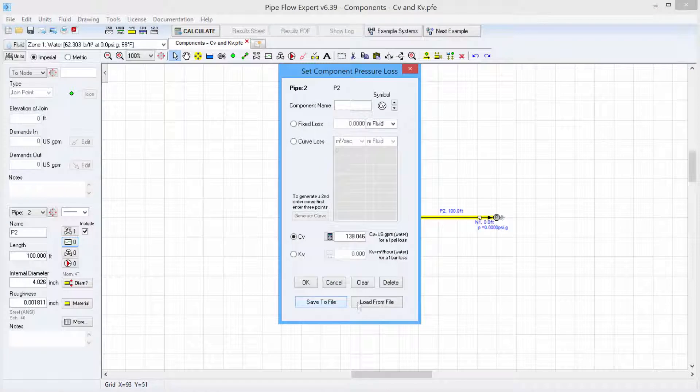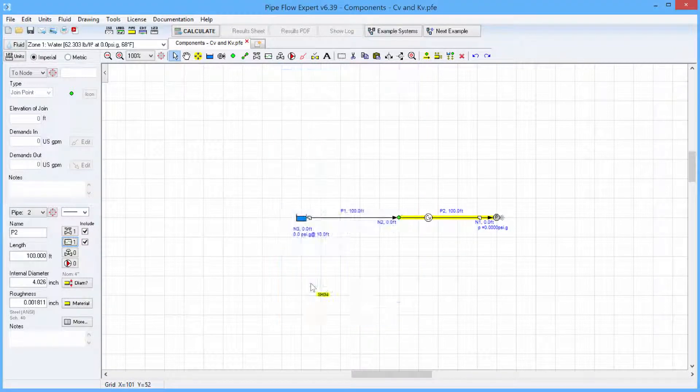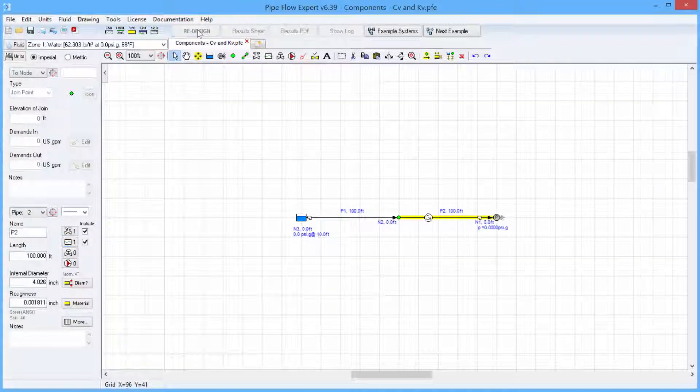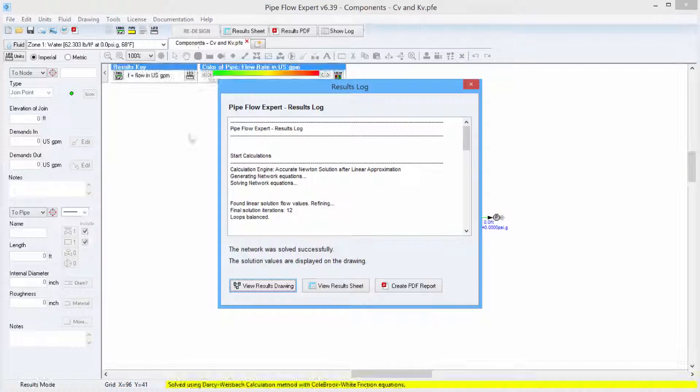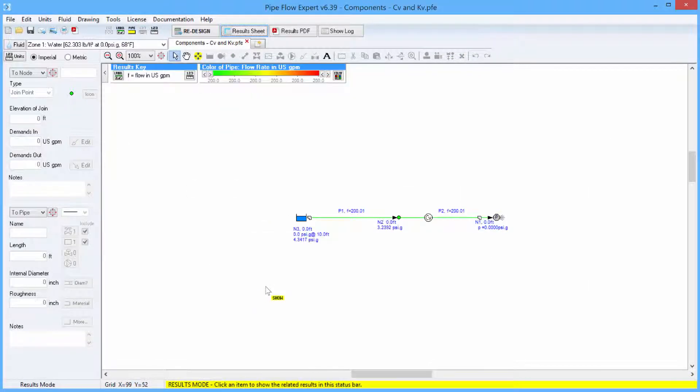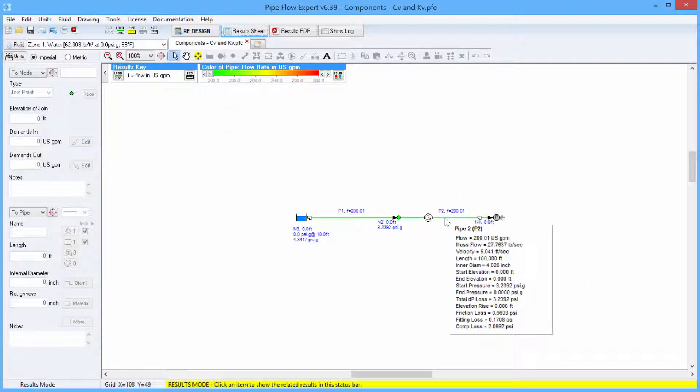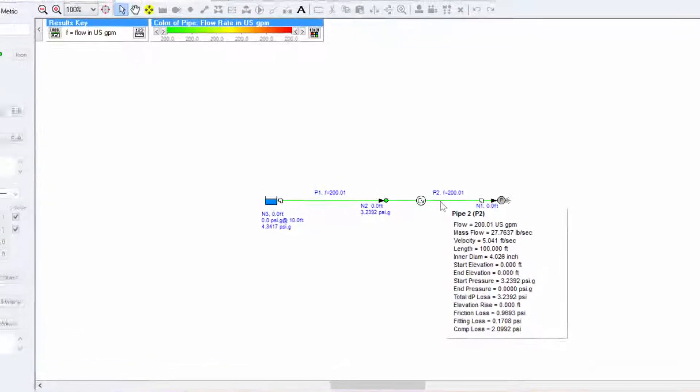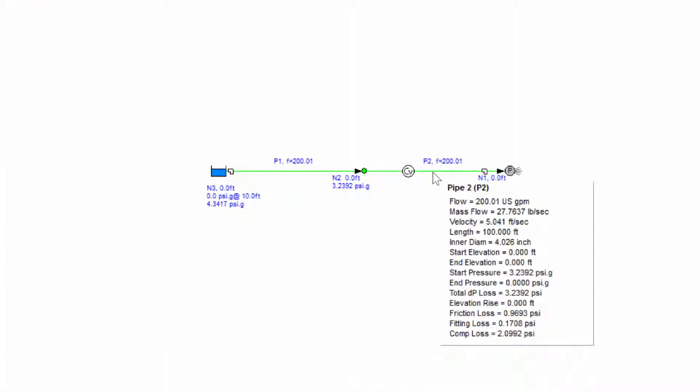So let's save this to the system. Click the calculate button. View the results drawing. And we can see that that component with that particular CV value that we calculated is controlling the flow at 200 US gallons per minute.